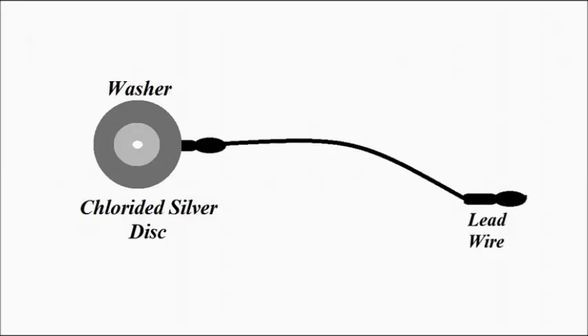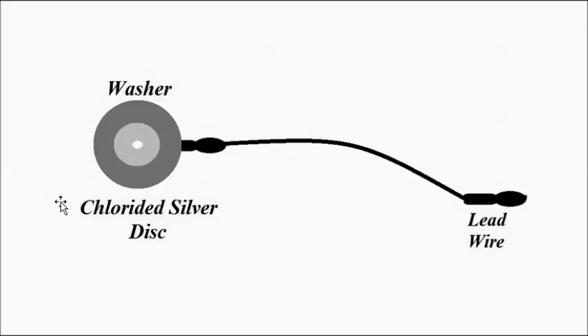The chlorided silver disc electrode consists of the silver disc electrode and a washer of a particular thickness. It is placed on the scalp so that the scalp never touches the electrode directly, which neutralizes the effects of motion artifacts, sweat, perspiration, and high pressure. A lead wire conducts the electric potential and feeds it to the signal conditioning and processing circuitry, and then to the output unit.